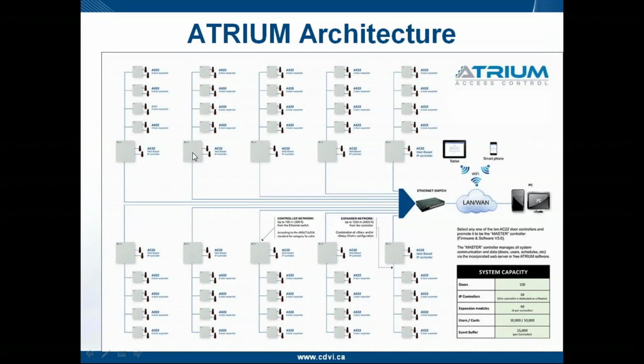These schedules will continue functioning as per what was programmed when the system lost communication with it. Whatever was there at the time of the failure continues to function 100%. Of course, if I want to add or change something, I need to reestablish communication with that particular panel. I have to correct the issue that I'm dealing with. However, what was there when the failure occurred continues functioning.